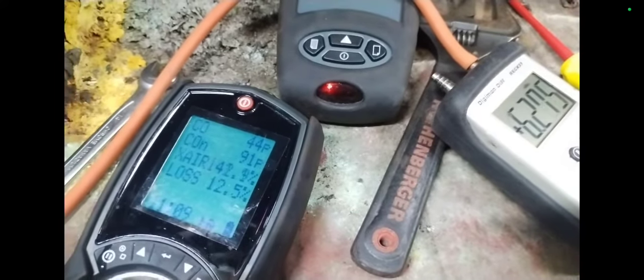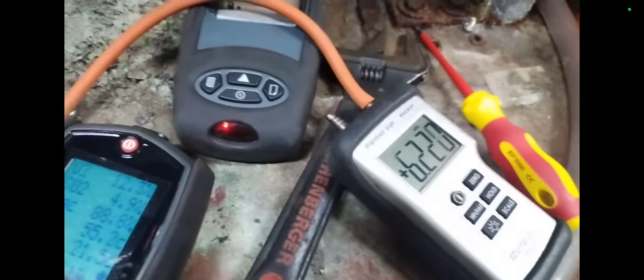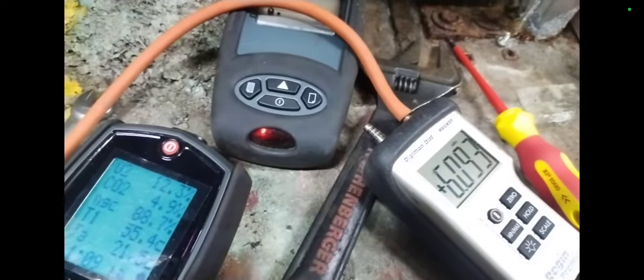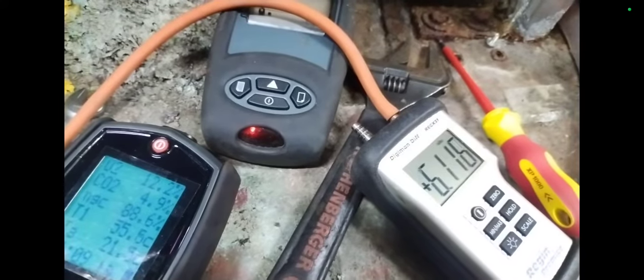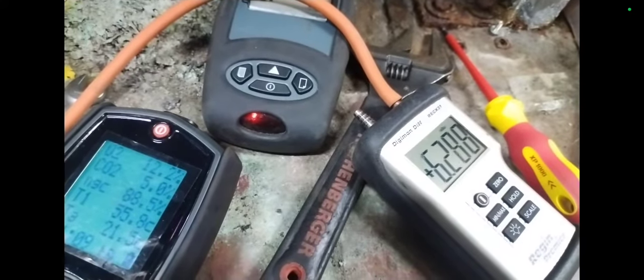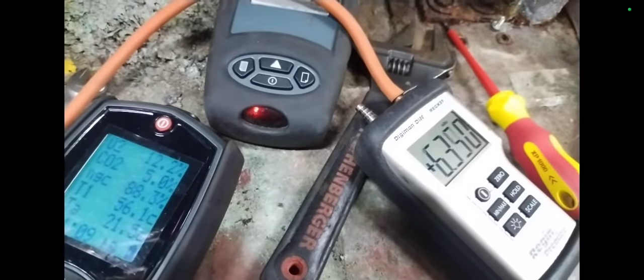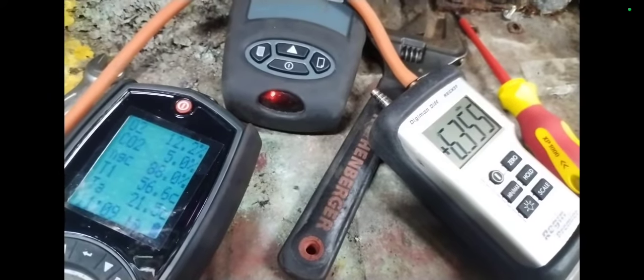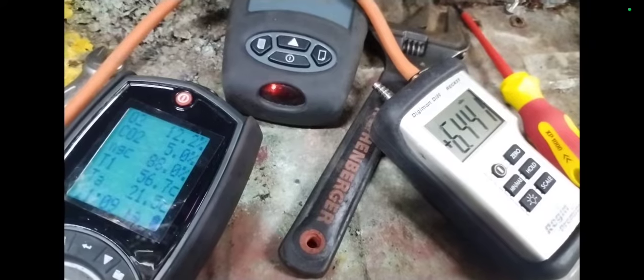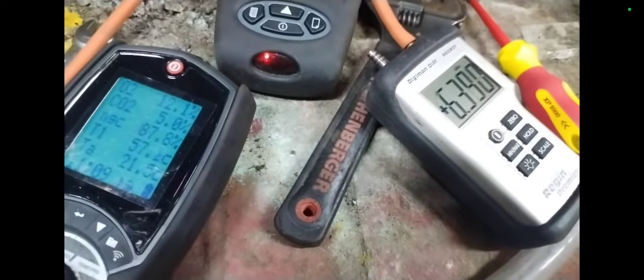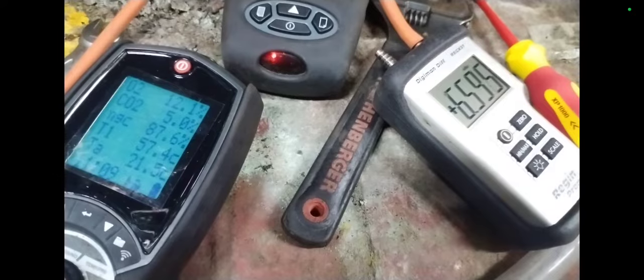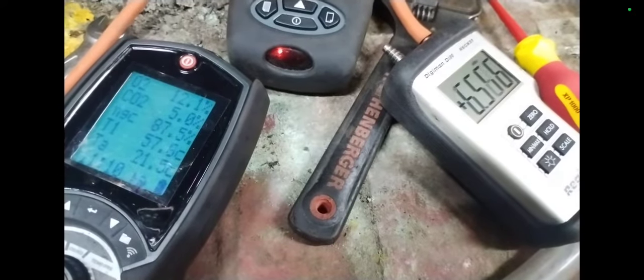I will double check. And here is me making adjustment on another one. I've got 6.2. It's the one on the far right. It's the one on the bottom right. I'm going to tweak up the burner pressure to 6.8. So I think the one on the bottom left, I had 4 modules here. The one on the bottom left started to, it was lighting initially, but then when I made an adjustment to the burner pressure and tweaked it up to 6.8, it stopped lighting well. So I may have to tweak it down a little bit for it to light well, but I've just turned that one off for the time being.